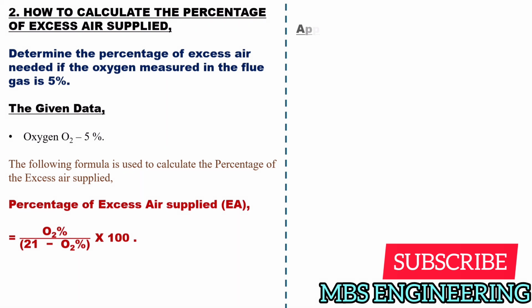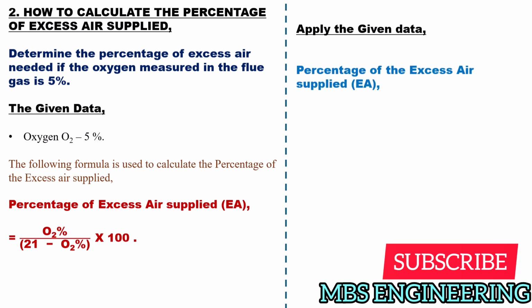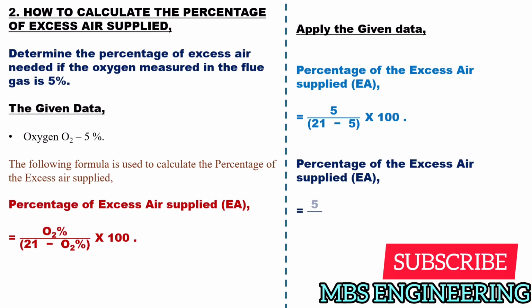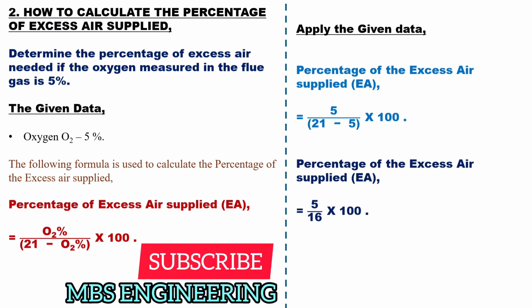Apply the given data. Percentage of the excess air supplied, EA, is equal to 5 times 100, and then the obtained value is divided by 21 minus 5. Next, percentage of the excess air supplied, EA, 5 times 100, and then the obtained value is divided by 16. Therefore, the percentage of excess air supplied, EA, is 31.25%.